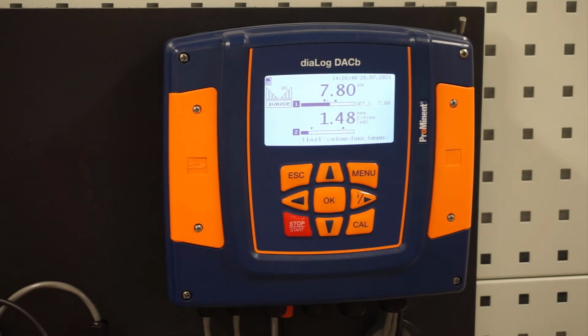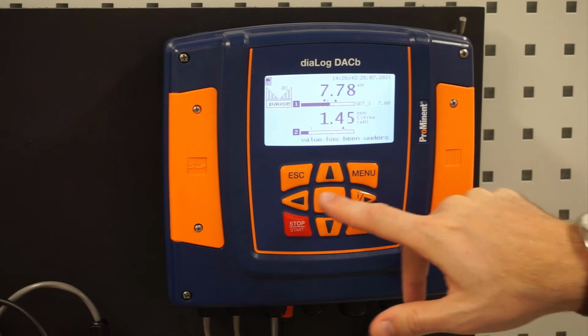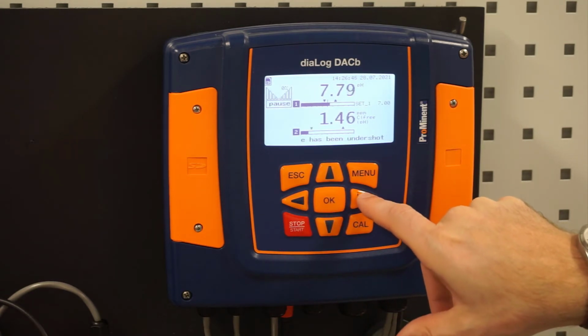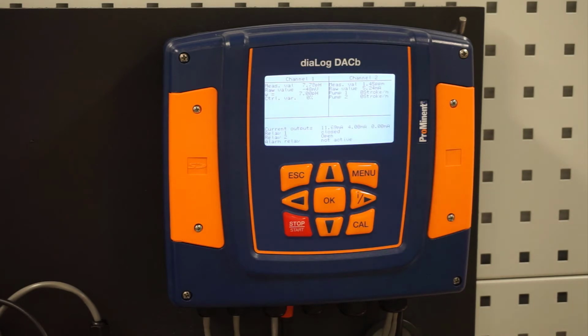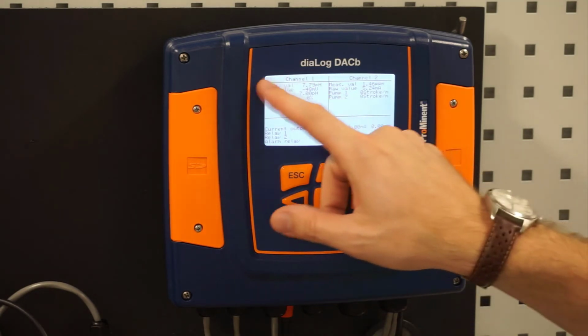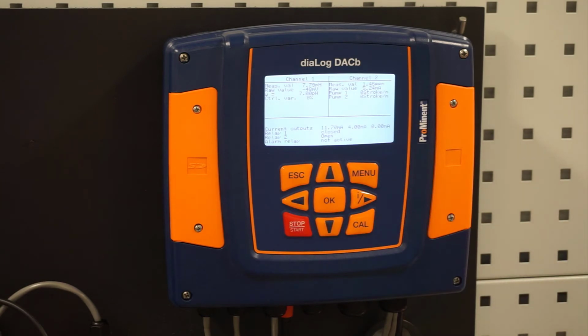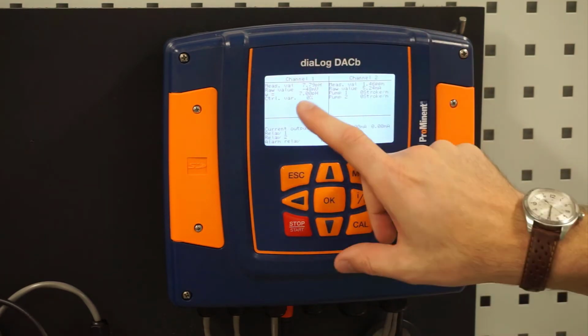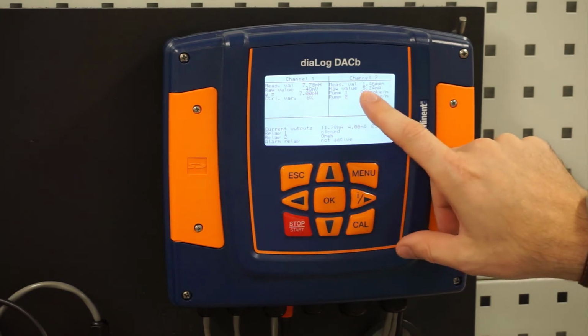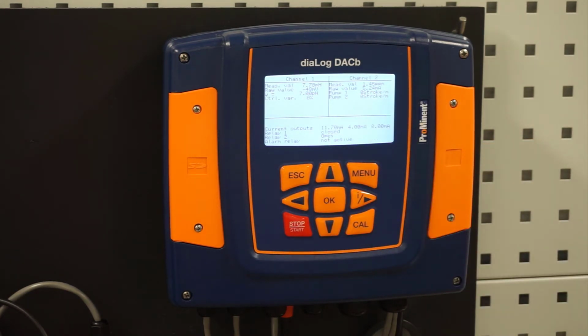So let's go through some of the menus. First thing, a very helpful tool is if I hit the I key, that will take me to my information screen. From there, I see the raw value of what my sensors are seeing. This is a really good screen for troubleshooting. If you were to call into the Prominent service line, they would most likely want you to access this screen so they can see what the raw value of the sensors are, so they can determine if it's reading correctly. Maybe it's been calibrated too many times. Maybe the electrolyte's ready to be replaced. Maybe your pH sensor has expired its lifetime. It's time to replace that.